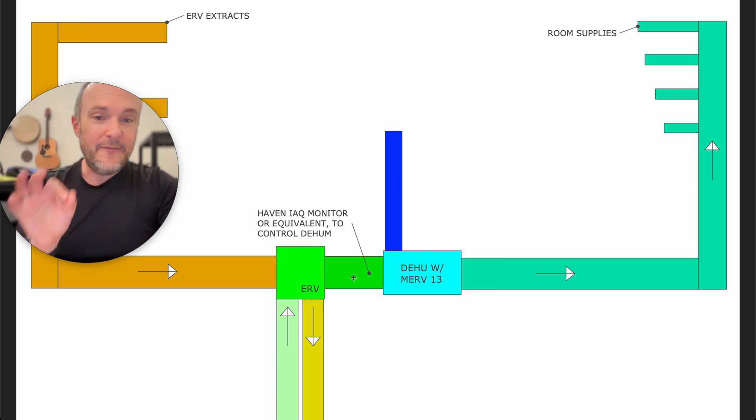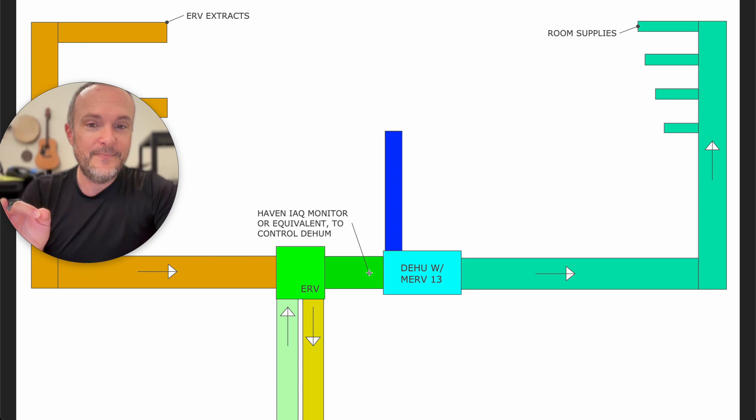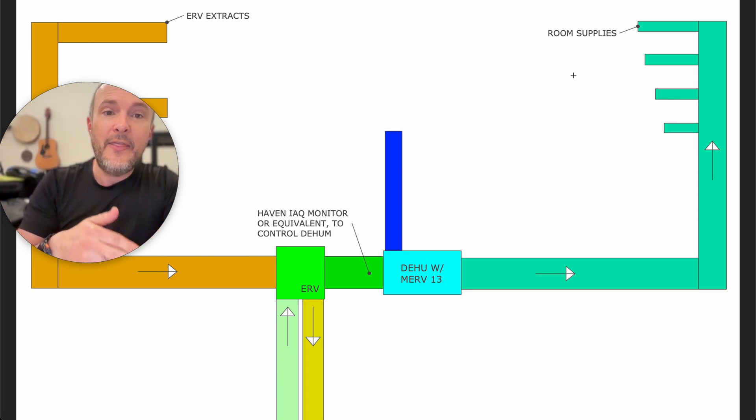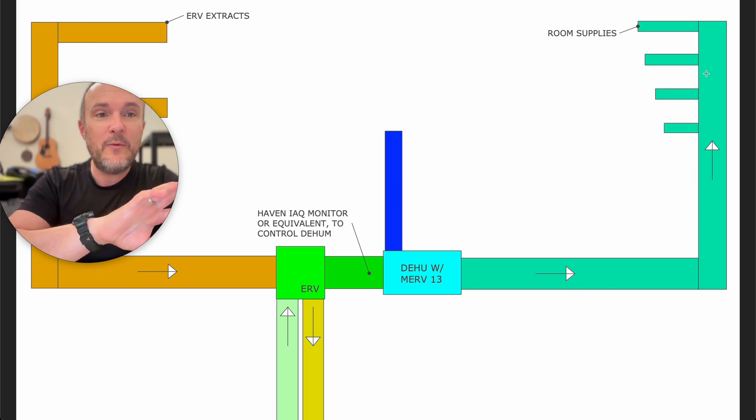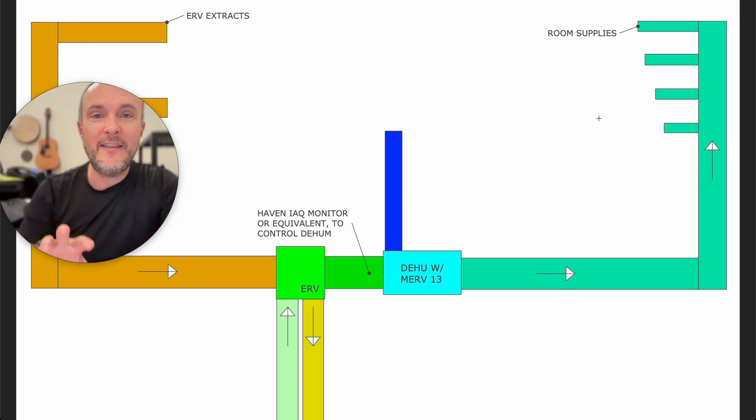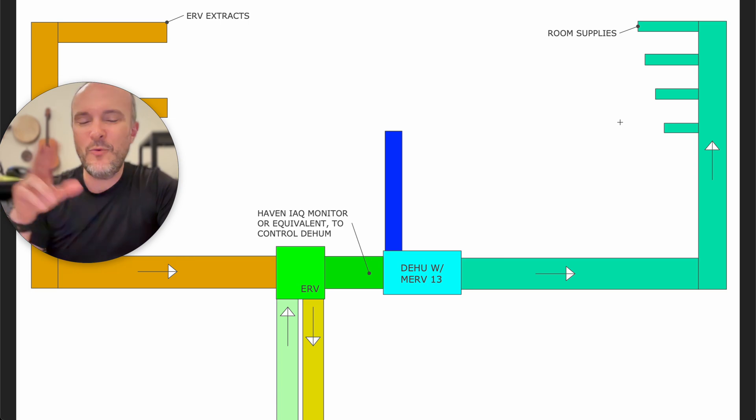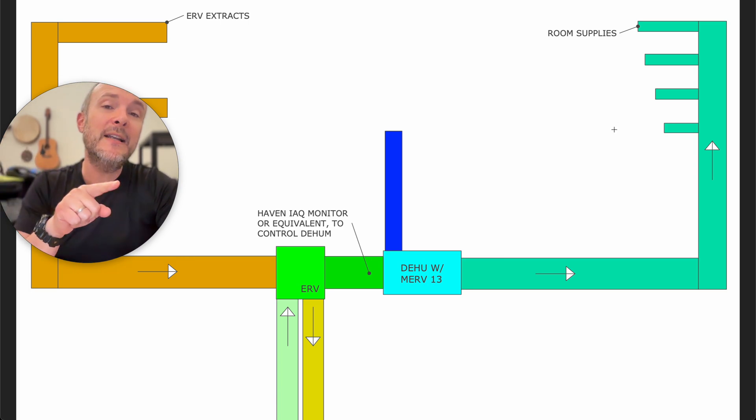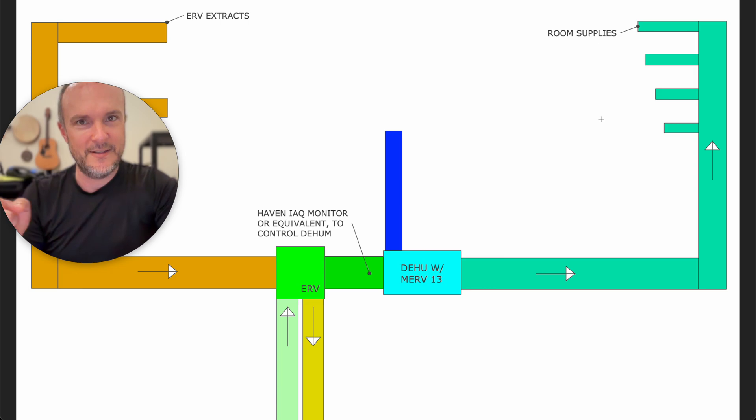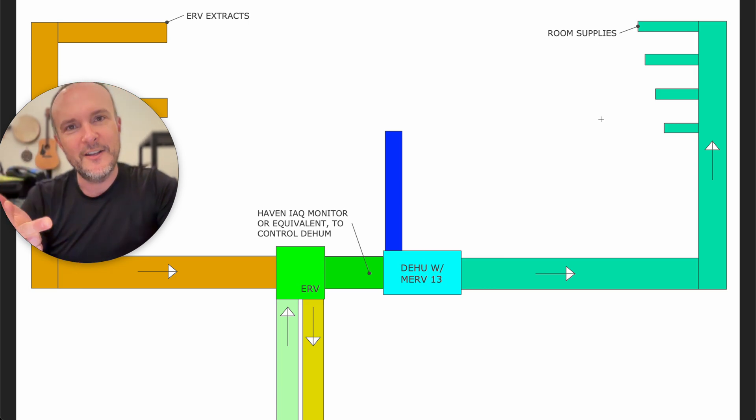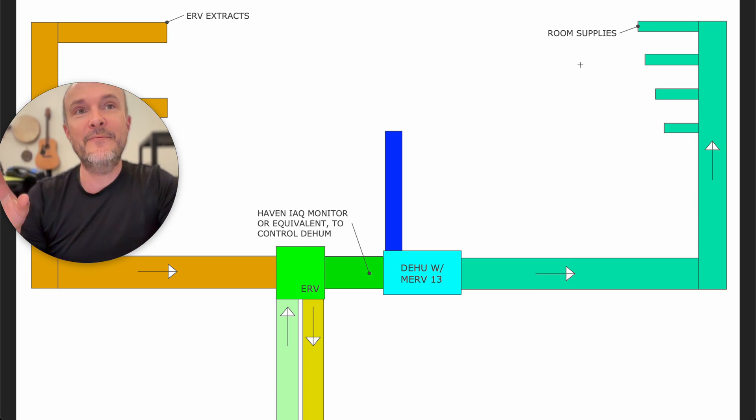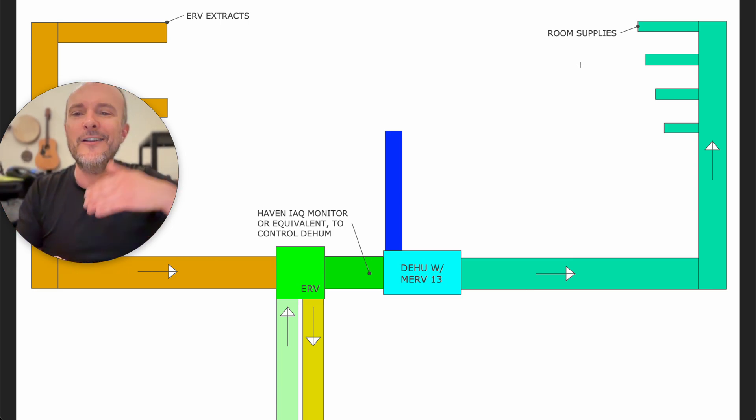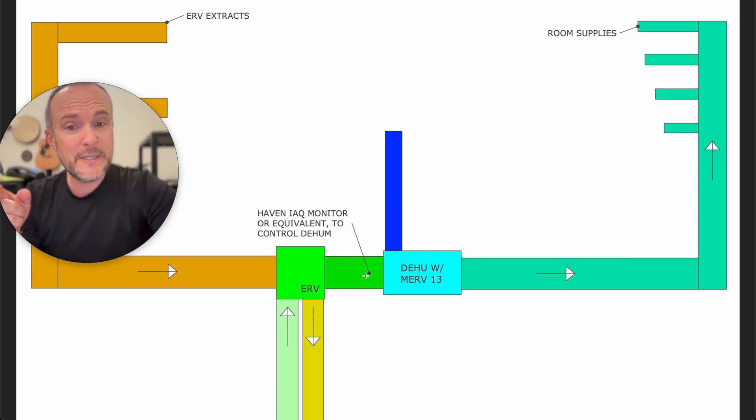If you didn't do that, if you put the sensor out here in the room, then the air would go through here and it would be wet, wet, wet. It would start wetting everything in the house and building up the humidity. But the humidity more importantly will be going into the solid materials: your couches, your curtains, your floor, the drywall, things like that. And then the humidity stat will say, 'Oh hey, it's humid in here,' and you'll have to now play catch-up. That's not what you want.